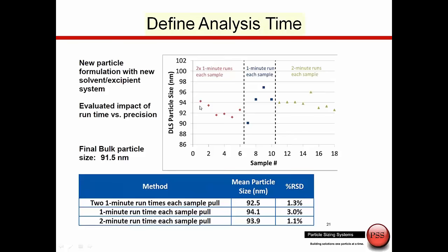The first thing we looked at upon installation was how long to perform the measurements. For narrow distributions you can do quick measurements; for broader distributions you have to take your time. We looked at the effect of taking two one-minute runs and averaging, then one-minute runs alone, then two-minute runs. The decision was based on percent RSD — standard deviation divided by the mean, normalized and multiplied by 100. What we saw is that for the two-minute runs we had the lowest RSD, so we decided for this process we'll take measurements every two minutes.